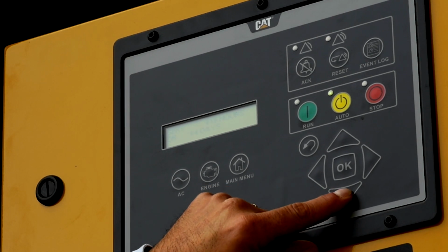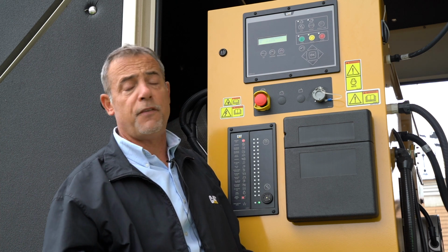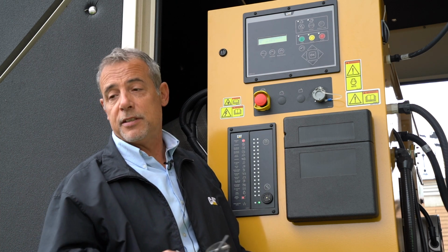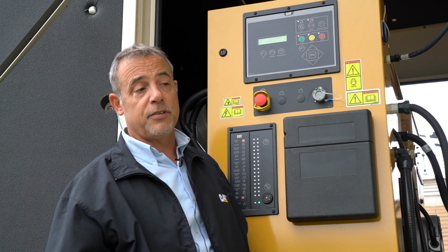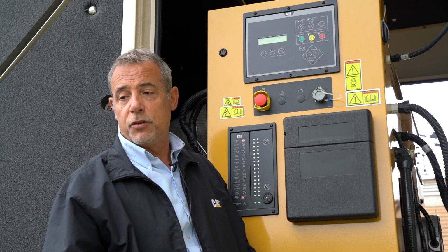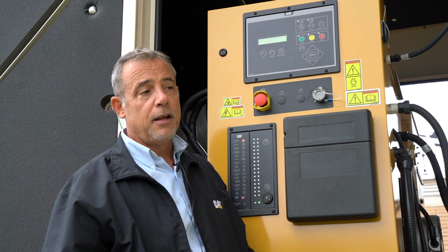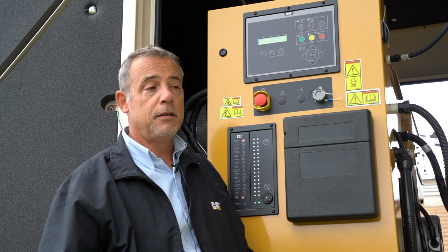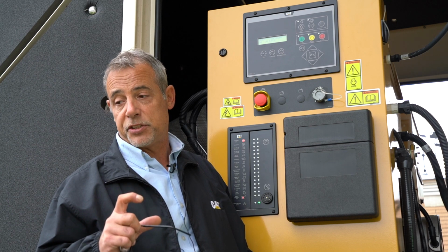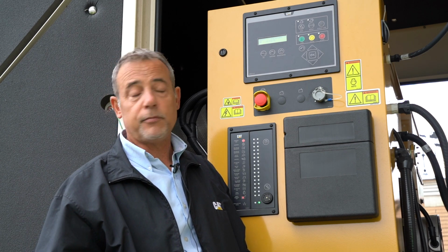The fourth page is a service interval. That runs on time or hours. Basically, you're supposed to change oil at 500 hours. You'll never put 500 hours on, so it's on a time period. And it's set to a year, 365. We turn that function off because a lot of people don't change their oil once a year, although we recommend it. CAT says you could go 3 years without an oil change as long as you get live oil samples taken and send it to a lab and have the records of it.